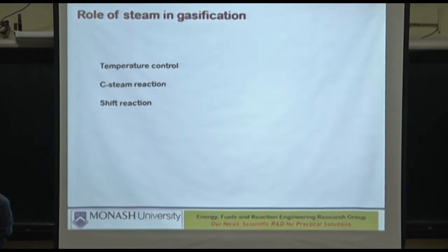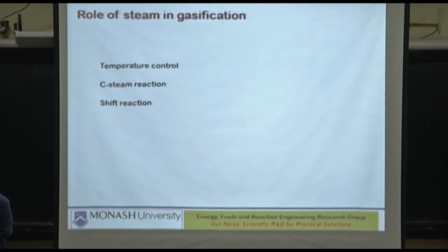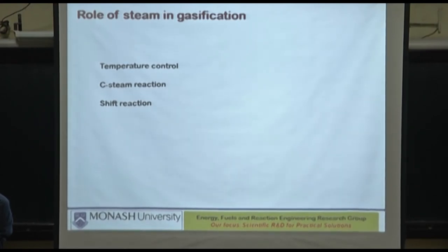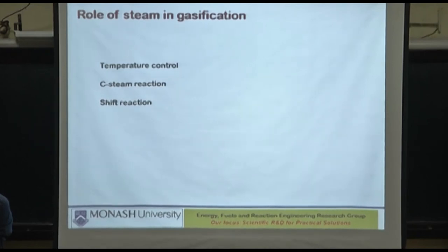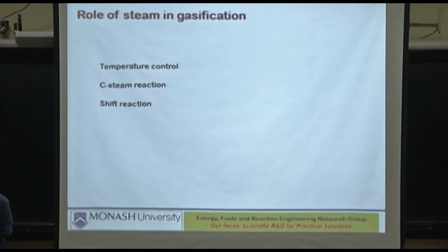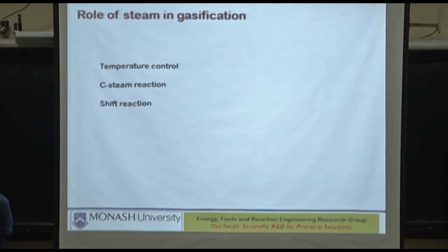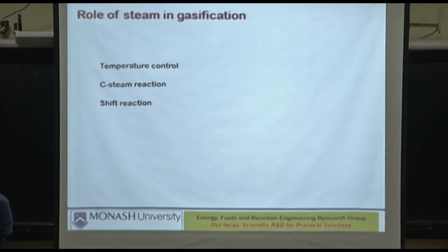And that's not done out of scientific curiosity. It's done for a proper reason. The point is, if you are preparing your char at high temperature, then invariably that char will have less reactivity for all sorts of reasons. Therefore, you will need higher temperature in the gasifier. That's another reason why the majority of the large gasifiers are entrained flow gasifiers. That's one of the reasons.